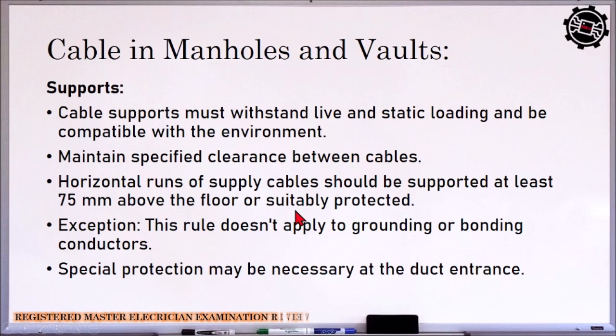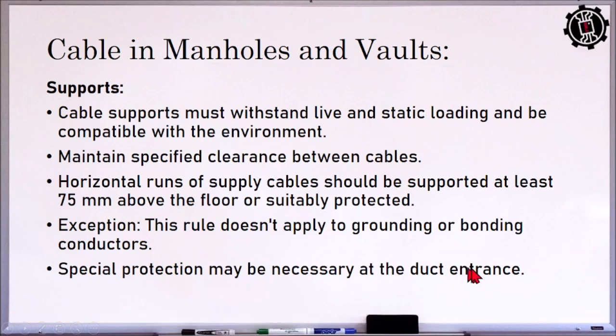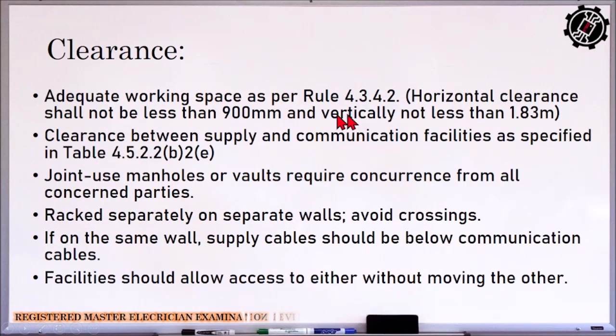Special protection may be necessary at the duct entrance. So at the entrance of our ducting, we should put special protection to prevent damage to our cable. So clearance. Adequate working space as per Rule 4.3.4.2. This was the last time. The horizontal clearance shall not be less than 900 mm and the vertical clearance not less than 1.83 meters. So this is the adequate clearance for supply cable underground.